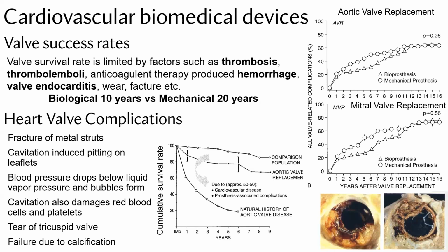Maybe for a couple of minutes, okay? So operating under the blood flow, the pressure, the fatigue cycling, because you constantly cycle from high to low, high to low, these really make it hard for these materials to survive. That's why metals are really good. Plastics have issues. And so, all sorts of issues can happen, but cavitation is a big one there.